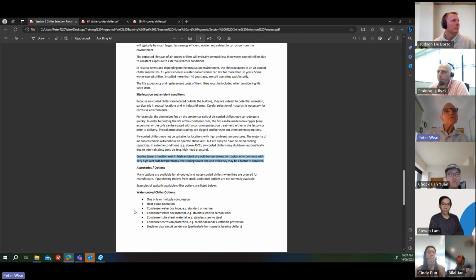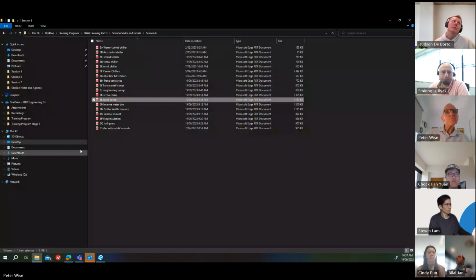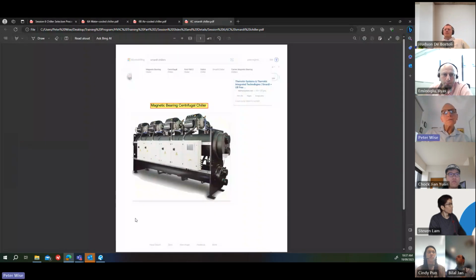I've got a few more slides I can show you of different types of chillers. This is a water-cooled chiller with magnetic bearing compressors. These are centrifugal compressors, and you can see there's 4 compressors there. So you can keep building these chillers up to whatever capacity you want. And I have heard recently that you can get up to 10,000 kilowatts. So they've developed a compressor where each compressor is 1,000 kilowatts capacity. And with 10 of those sitting on top of the machine, you've got 10 megawatts.